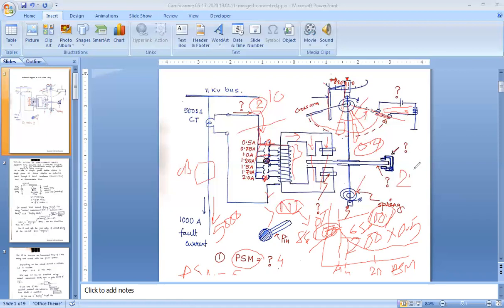So the relay will operate at this time. So the operating time is 2.4 seconds as it is set at 0.4. Had it been set at 1, then it would be 6 seconds. As the time is set at 0.4, it is 2.4 seconds. So it should be the theoretical value.